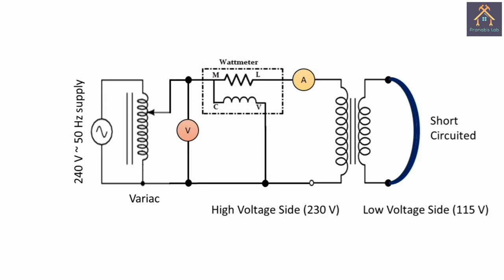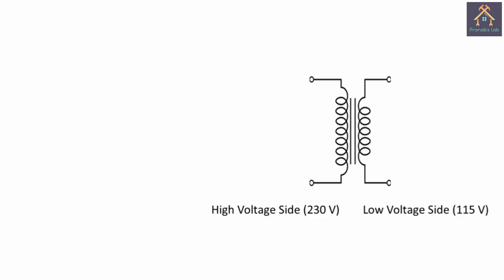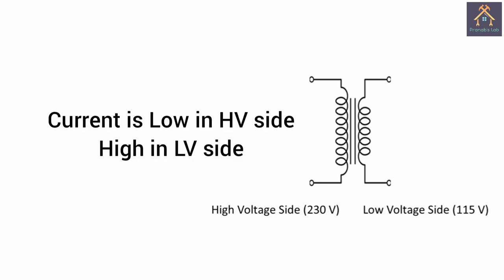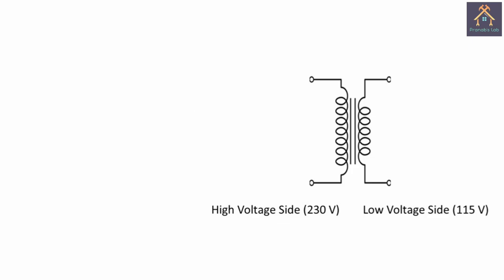Now let's connect it virtually. For this experiment, we need a 230 volt by 115 volt transformer. The high voltage side of the transformer will be connected with the measuring instruments and the low voltage side will be short circuited, because the rated current will be lower on the high voltage side compared to the rated current on the low voltage side. So the low voltage side should be shorted.